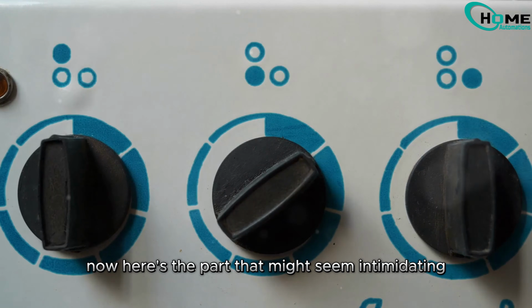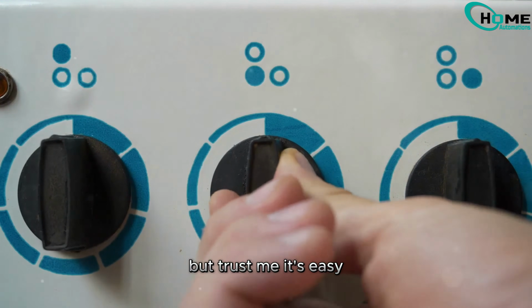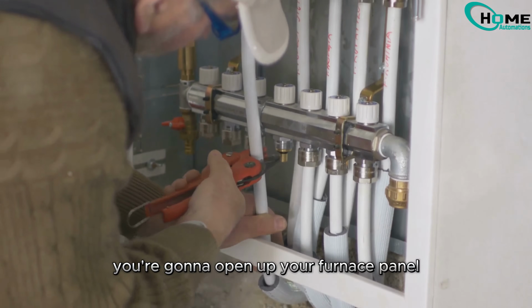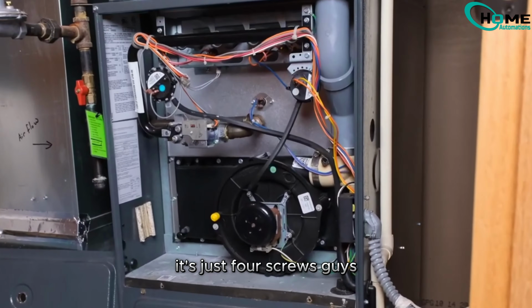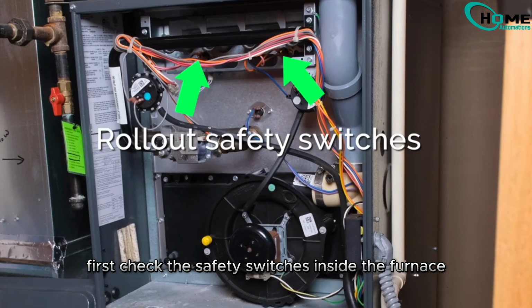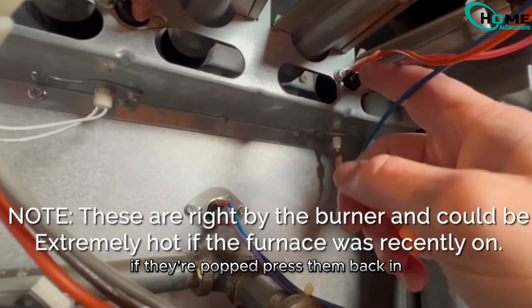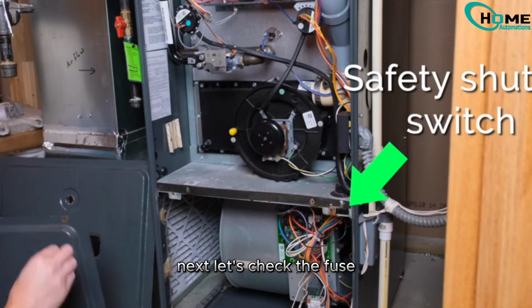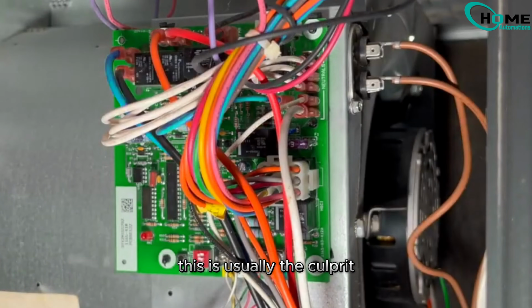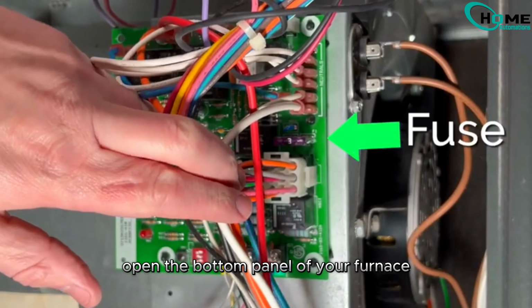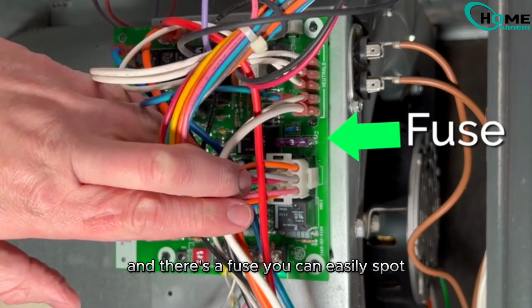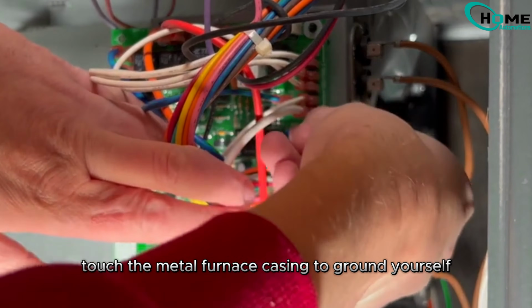Now here's the part that might seem intimidating, but trust me, it's easy. You're going to open up your furnace panel. It's just 4 screws, guys. First, check the safety switches inside the furnace. If they're popped, press them back in. Next, let's check the fuse. This is usually the culprit. Open the bottom panel of your furnace and there's a fuse you can easily spot. Touch the metal furnace casing to ground yourself, pull out the fuse, and check if it's blown.